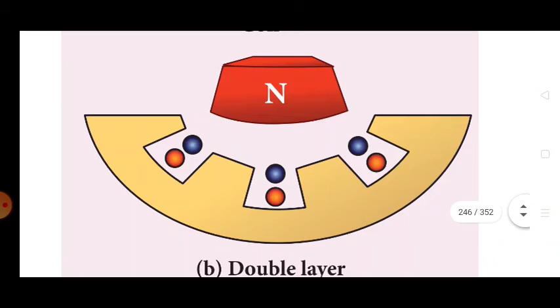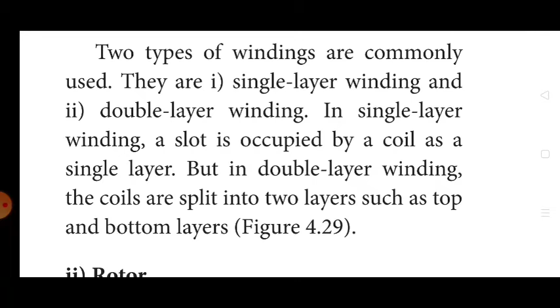Generally, when looking at types of windings, they are single layer windings and double layer windings. In single layer windings, a slot is occupied by a coil as a single layer. But in double layer windings, the coils are split into two layers, such as top and bottom layers.